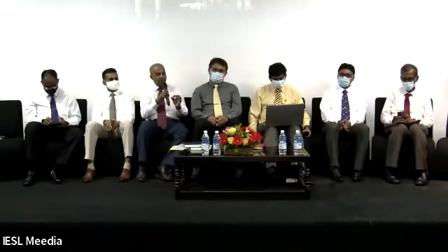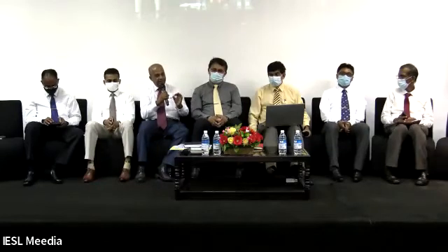Thank you. I think we are putting too much focus on the most unimportant thing in the whole scheme of things, because nobody has suggested, including the committee, that somebody has created an earth fault, right? And we have said, even in our interim report and also in the final report, that the indications of the fault from the relay records as well as disturbance recorder reports are consistent with a high impedance single line earth fault. Having said that, as the Professor said, with single line faults, in 80% or even more you cannot find a cause. It is the case here also.